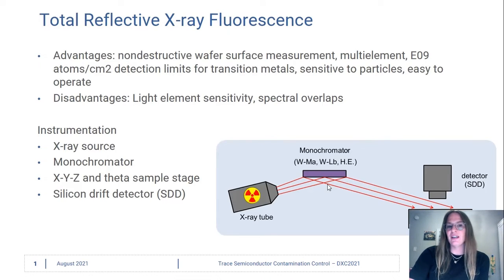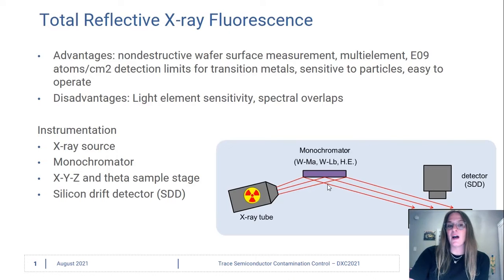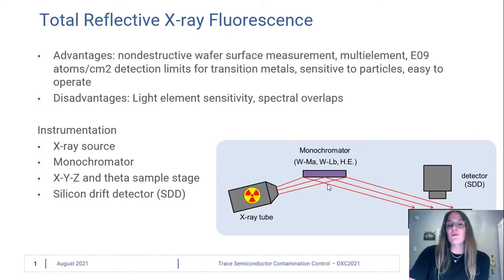The instrumentation includes an x-ray source and a monochromator for our incident x-ray beam. It also has a very precise sample stage with x, y, z, and theta movement, so we can have very precise and repeatable alignment of the wafer substrate to the x-ray beam. Also a silicon drift detector.